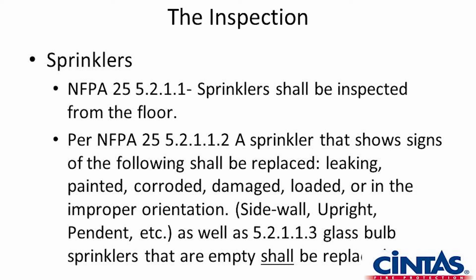The seat is what holds the water back, and the glass bulb or the fusible link is what prevents the tip cap, as it's called, from releasing to allow water to flow. As corrosion builds, it locks that tip cap into place. So even if the solder link does melt or the glass bulb does break, there is a delay in the operation of the sprinkler. It's called the RTI, the Reaction Time Index, and sprinklers are classified as either quick response or standard response based on their RTI, their reaction time.